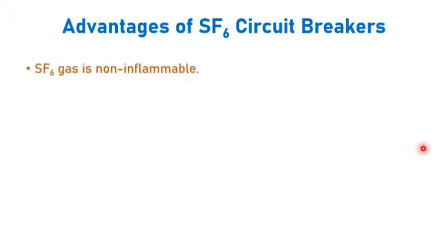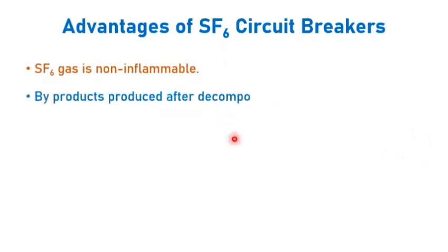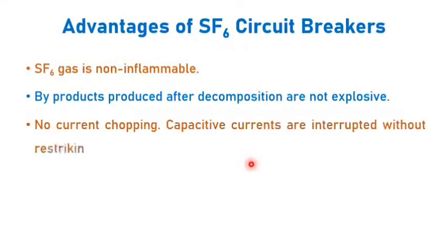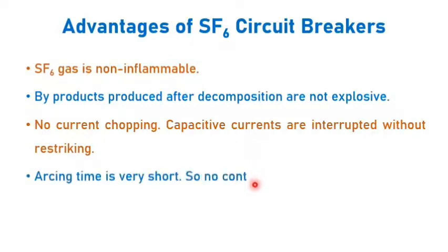Advantages of SF6 circuit breakers. As I said before, SF6 gas is non-inflammable and the byproducts produced after decomposition are not explosive, and no current chopping is possible and capacitive currents are interrupted without restriking. In the previous video I told you about current chopping and capacitive current interruption. Anyway, we will discuss these two topics in further videos. Arcing time is very short because SF6 gas quenches the arc at a faster rate, therefore the contacts are very safe.